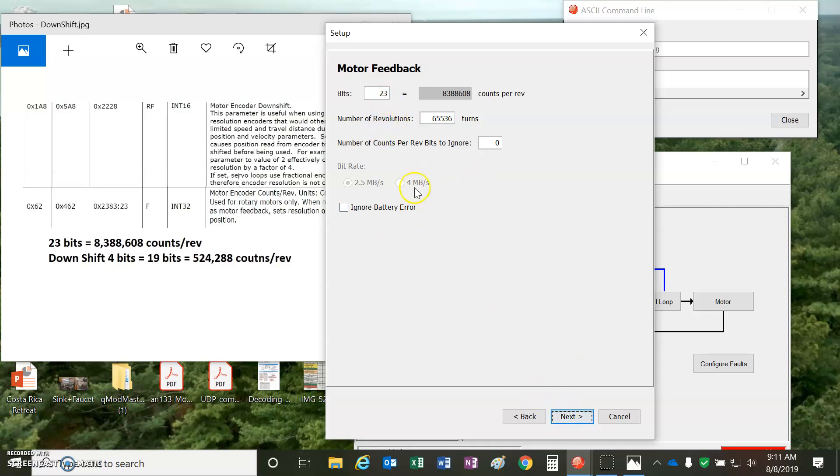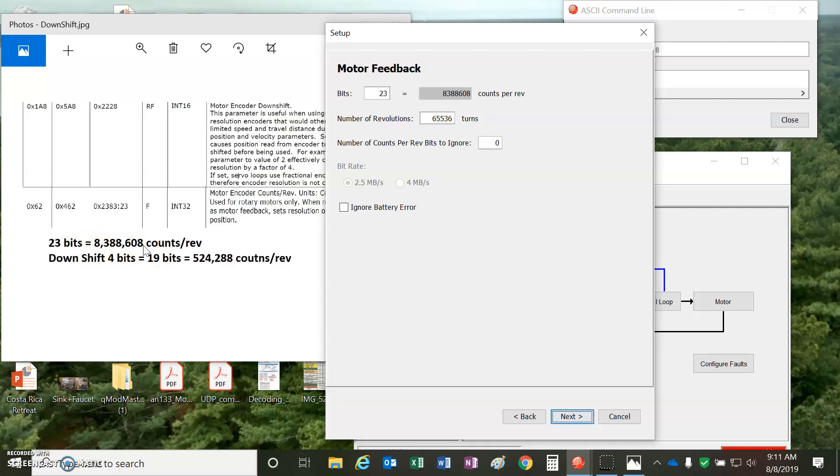I'll also note that the CME doesn't have the ability to downshift the encoder yet, and that's something that we'll do over the ASCII port. If you notice, a 23-bit is like 8 million counts per rev. Sometimes, the only thing we get with that many counts is just a larger following error. If you go really slow, that might be a benefit, or if you need the resolution, that might be a benefit.